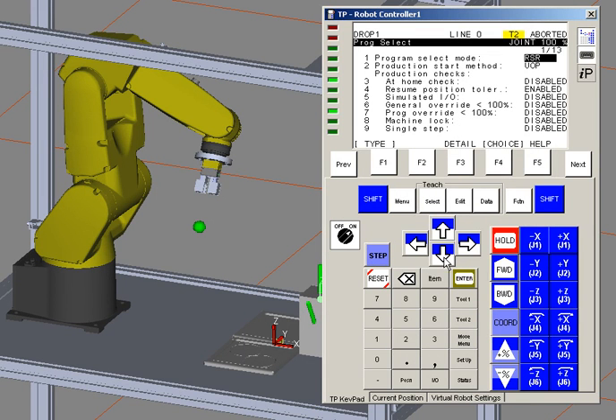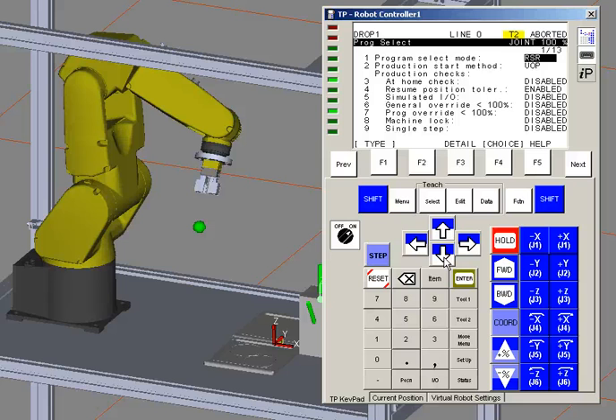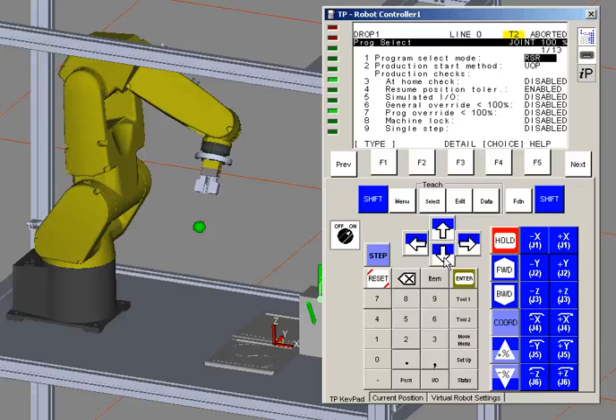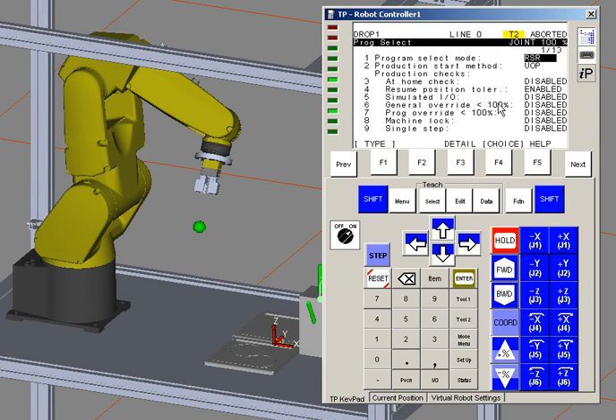For example, there are some instances when you tested and defined your program to run at 100%. If you were to run the system at slower percentages, override speed, the system would not function properly. Think of a painting process where you're set to paint a certain pace. If you slow the system down to 50%, you would put a lot more paint onto an area, and you just don't want that.